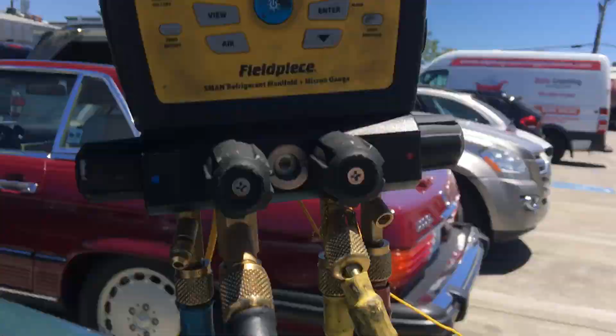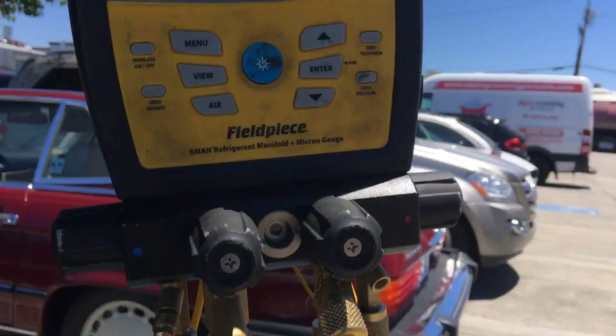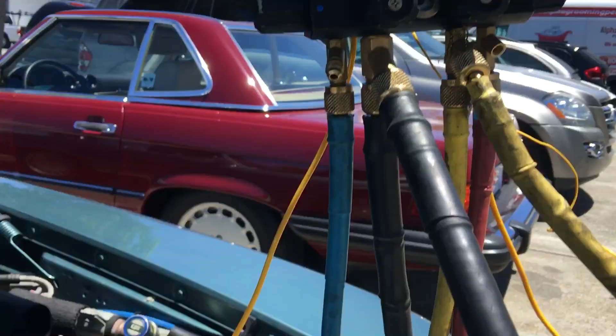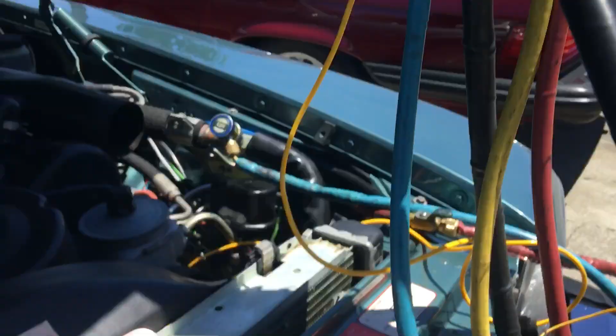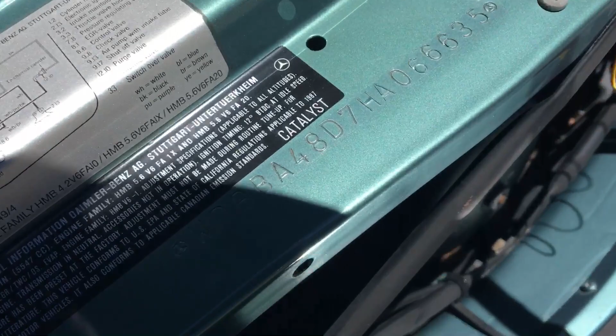That came on late. I noticed the high side was at 290 before that fan came on. That fan should have come on at 270, not 290. So that's a little high setting. Our switch right here for the fan is out of calibration. So this is kicking in at 290 instead of 270. But even so, we're a little warm coming back on the superheat, and yeah, not good. It's cooling right now, but it's going to suffer greatly if you hit 80, 90 degree temperatures.